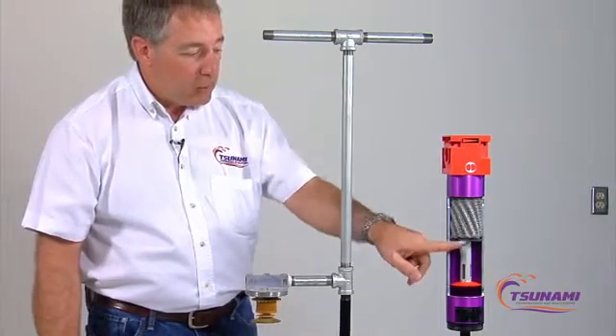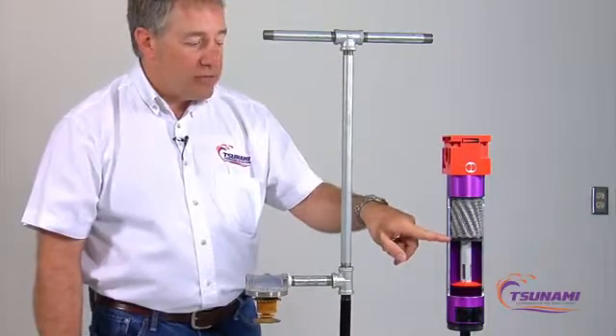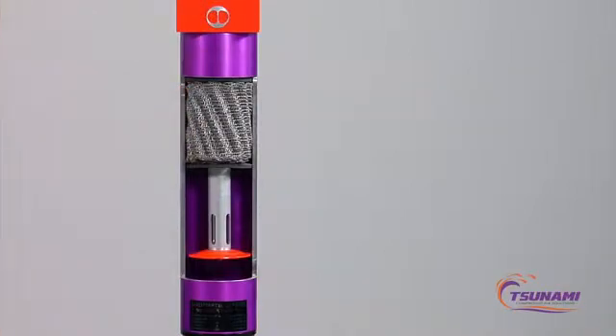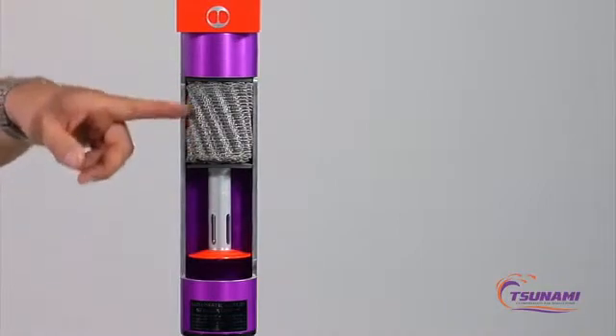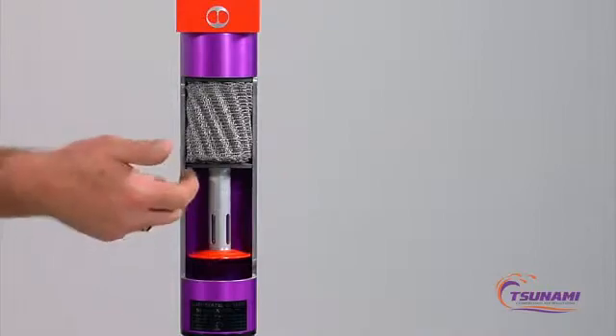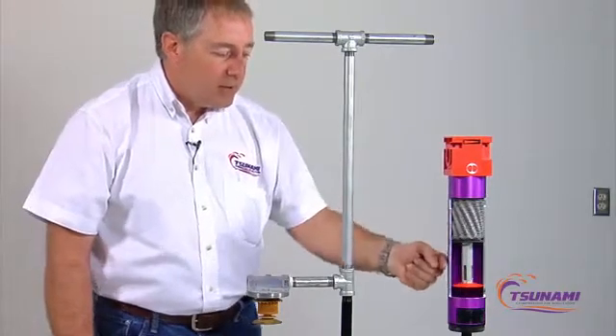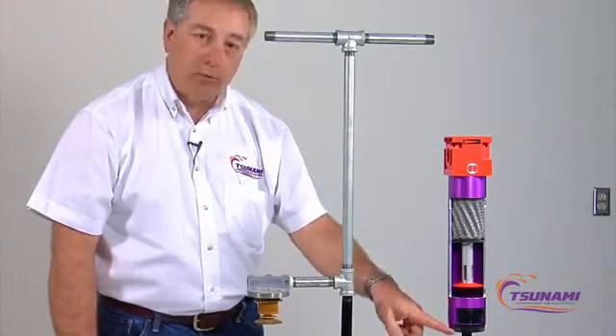When we come up here, we come up through this baffle plate right here, which has a series of holes. Now what we do is we accelerate the air coming up through this stainless steel mesh, something you never have to change, it's stainless steel. As the air comes up through here, it changes direction millions of times and it creates little vortices. And each time that air turns and spins, it coalesces out a droplet. That droplet, if you can see the spiral here, runs to the outside of the wall, and since we have a really low velocity coming up here, the water droplets are able to run down to the bottom of the drain sump where the automatic drain will eject them.